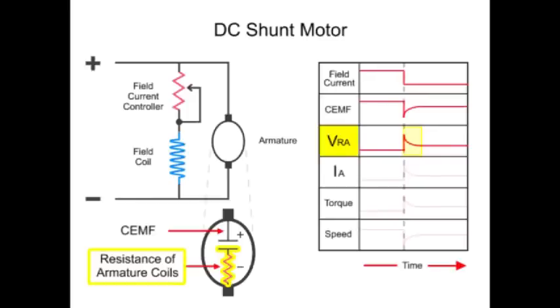Because the total applied voltage is across the armature, any change in the drop across one part of the armature, either the CEMF or the voltage drop across the resistance of the armature coils, VRA, will be made up by an increase in the drop across the other component.